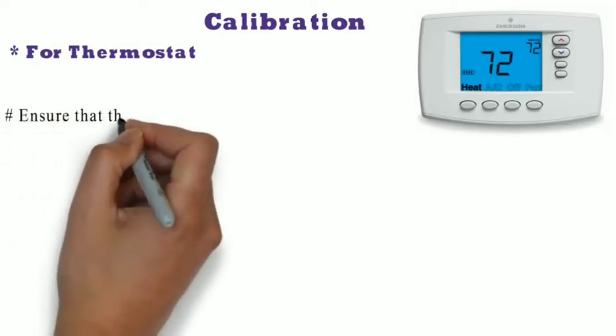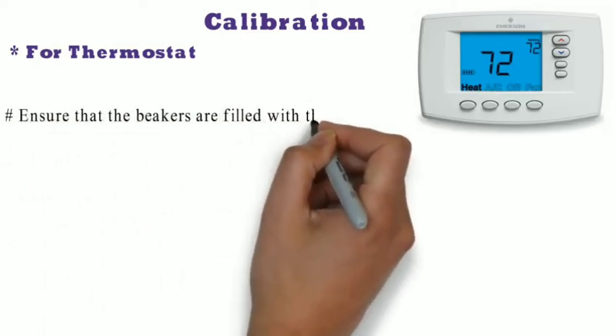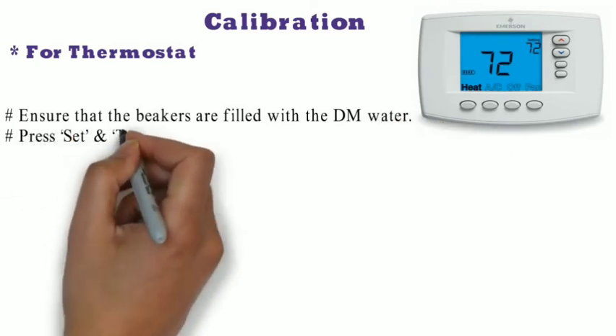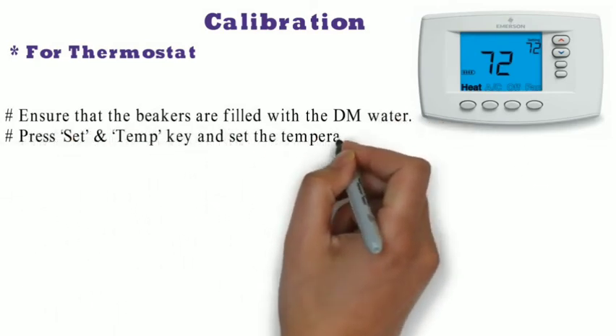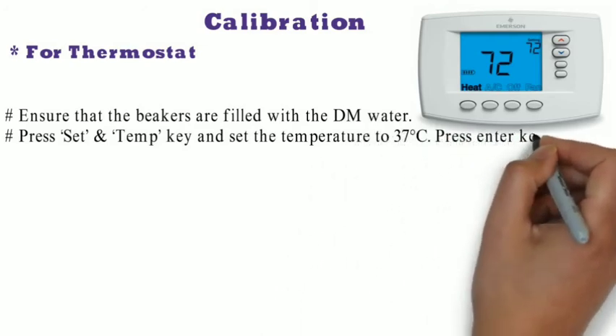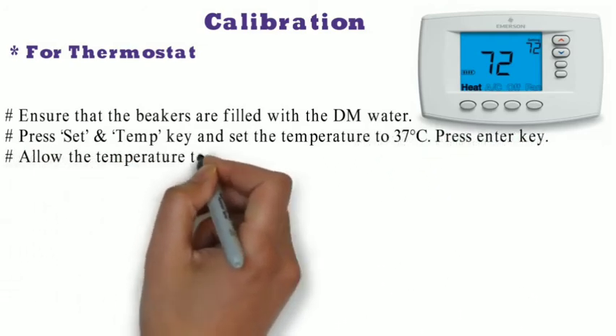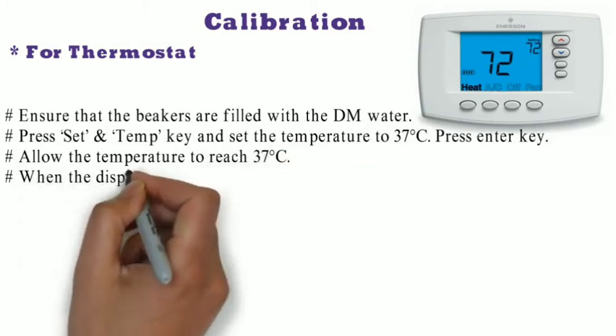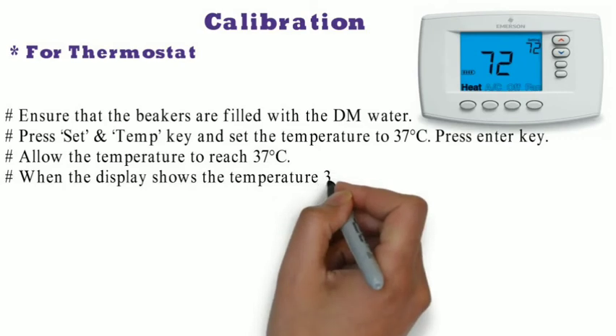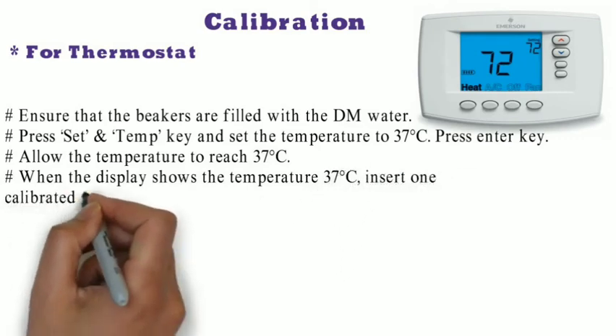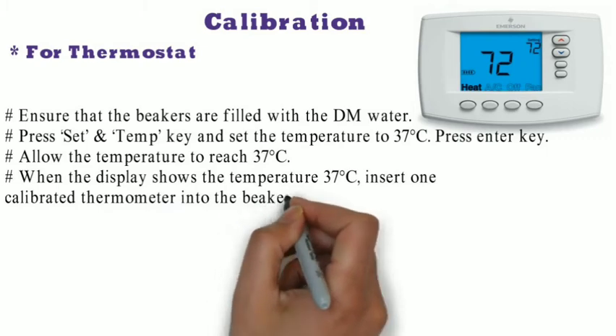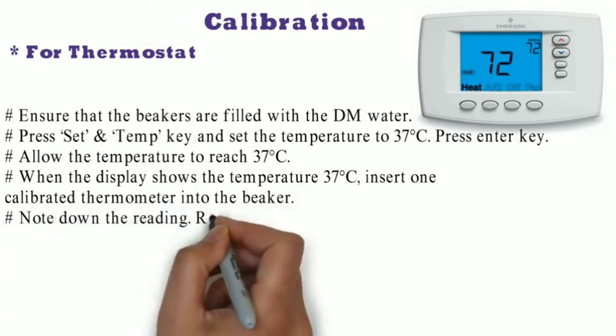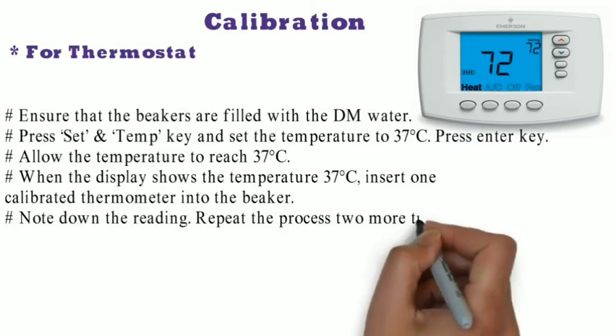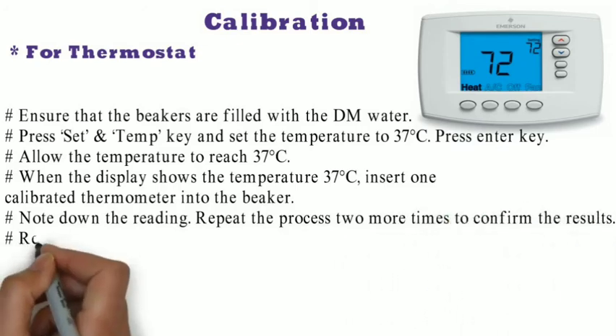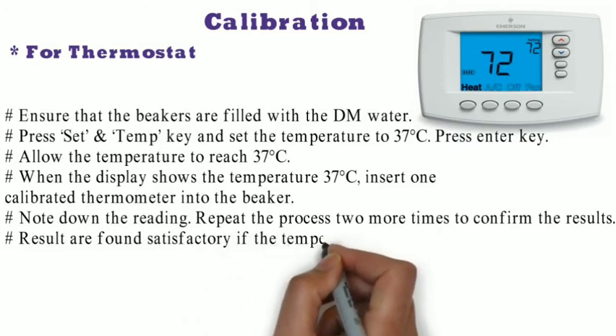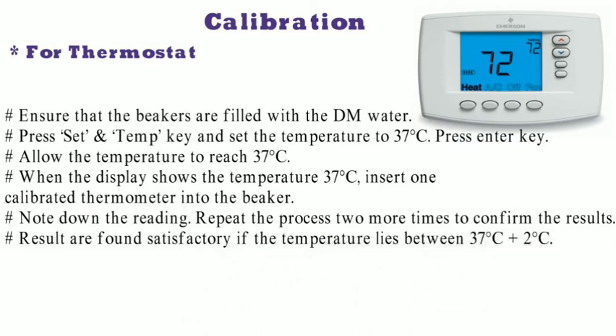Ensure that the beakers are filled with DM water. Press the set and temperature key and set the temperature to 37 degrees Celsius. Press the enter key and allow the temperature to reach 37 degrees Celsius. When the display shows 37 degrees Celsius, insert one calibrated thermometer into the beaker. Note down the reading and repeat the process 2 more times to confirm that results are satisfactory. The temperature should lie within 37 degrees Celsius plus or minus 2% deviation.